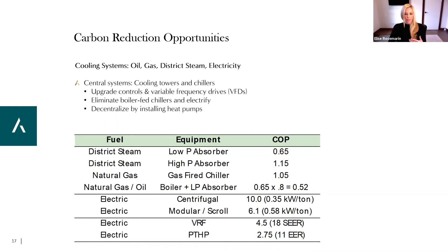On the cooling side, we're big advocates of getting rid of centrally cooled absorption chillers. As little as a few years ago we were looking at a lot of gas-fired equipment - old district energy steam low pressure absorbers, or natural gas/oil boiler plus low pressure absorber - and we were putting in a lot of direct gas-fired equipment.